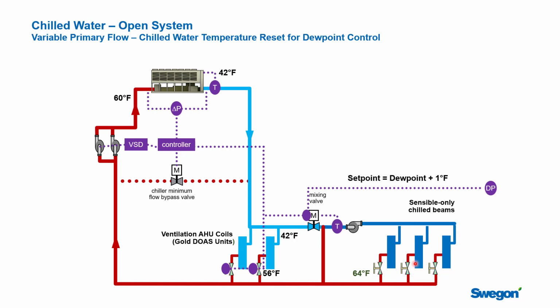Now, absolutely, if you raise your chilled water temperature, you're going to lose capacity at your beams, but some flow of warmer water is better than no flow at all. And so this would allow some relief to the occupants in the space. It does mean that you need to have dew point sensors in the space. You might not necessarily do this at the zone level. You might want to do this on a per floor or a large area.